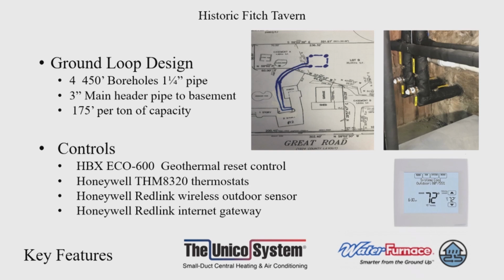All right. So to take a next step out into the ground loop, we did 4 450-foot boreholes. We oversized the main header, again, to try and minimize pumping power, which worked out to about 175 feet of borehole per heating ton of capacity.